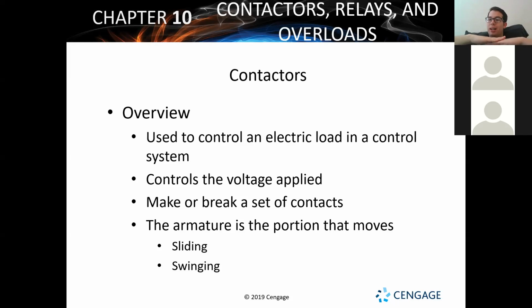When it closes and I turn my ceiling fan on, now from point A to point B, there's no load. There's no difference. It's just letting power pass through. So I should read 0 volts. We're going to get some testing to see how you guys can actually see and look at the components and see what happens when you're looking at an open versus a closed switch, an open versus a closed contactor, everything like that. Testing to make sure that a contactor, its whole job is to close and let power pass through, or to open and disconnect power.